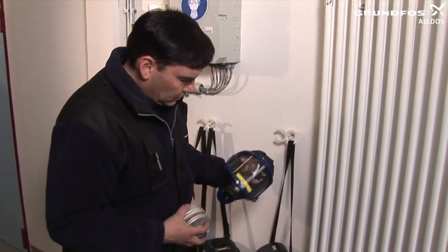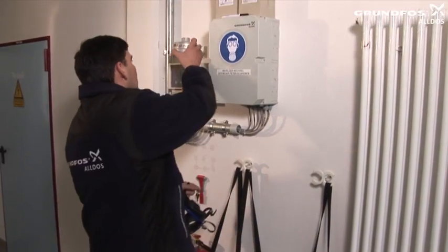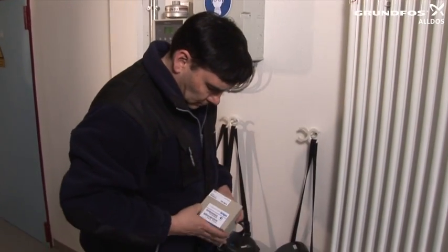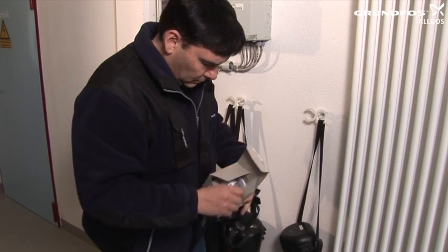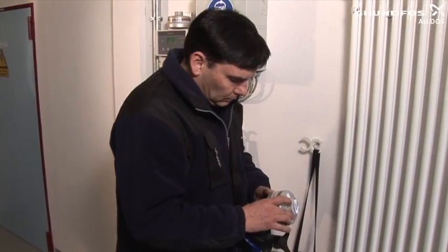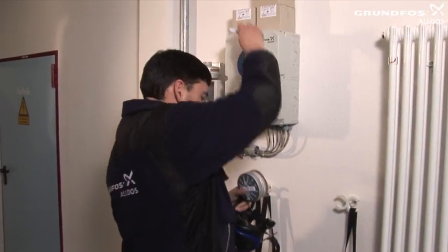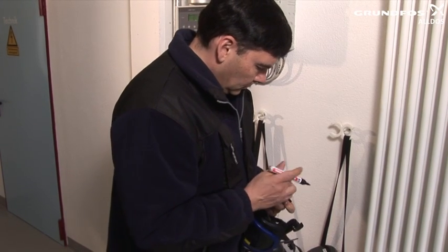The respirator mask is part of your personal protective equipment. In other words, it is marked with your name and must be stored outside the chlorine gas room. First of all, check the filter in the mask and ensure that the filter is still fit for use. If the filter has been in use or storage for more than 6 months, it must not be used under any circumstances. Replace it with a new one.